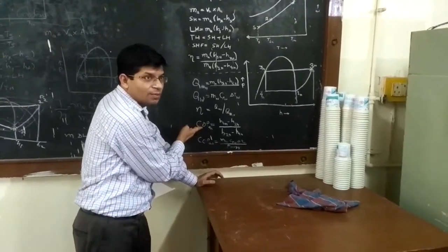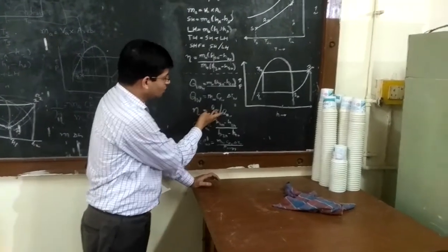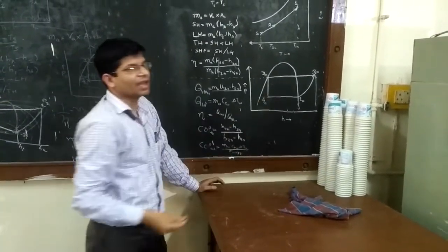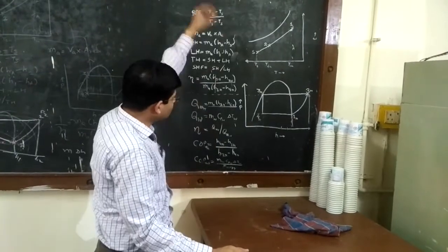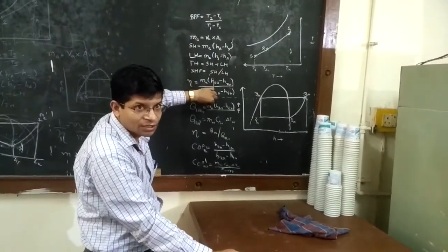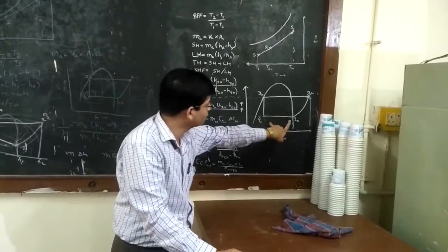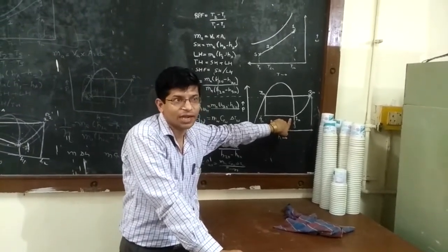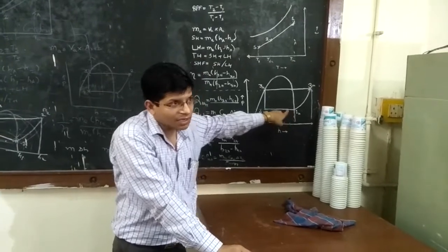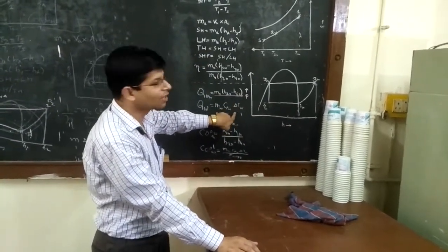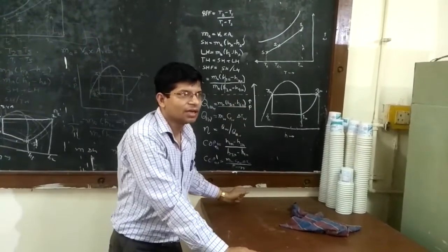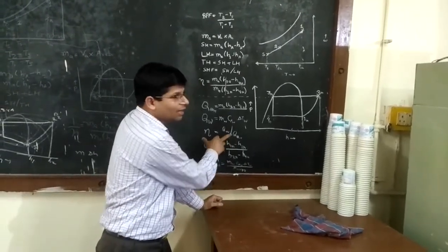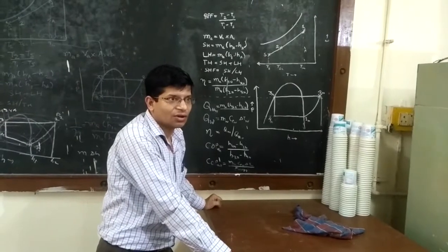This gives us the theoretical COP and the thermal efficiency. Thermal efficiency is determined by comparing the theoretical refrigerating capacity with the actual one. How much heat the refrigerant can transfer is given by M × ΔH, which is mass of refrigerant times (H1R minus H4R) — this is how much heat the refrigerant can take away. But it may have taken only part of that heat, so comparing these gives the thermal efficiency of the system. This was for the part when we are using this setup just for the calorimeter cooling.